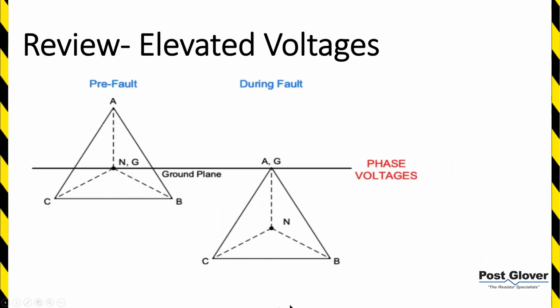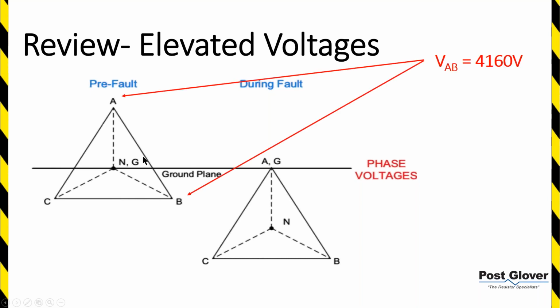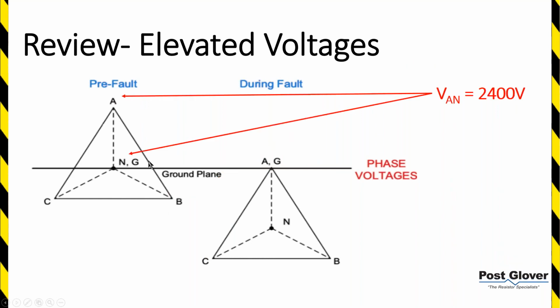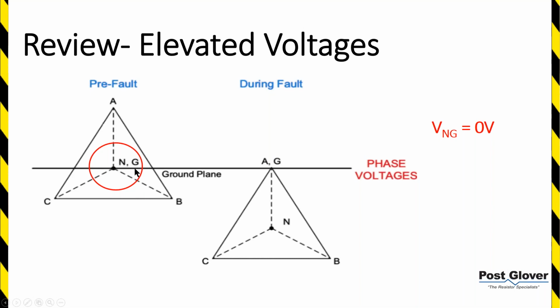So we have a voltage diagram showing the voltages as they relate to the ground plane. If you have your pre-fault or normal operating conditions, you're over here on the left-hand side. This is a medium voltage example. Our line to line is 4160, and our line to neutral is 2400. Of course, because your neutral and ground are tied together, you're going to have 0 volts at that point. What happens if you get a fault?